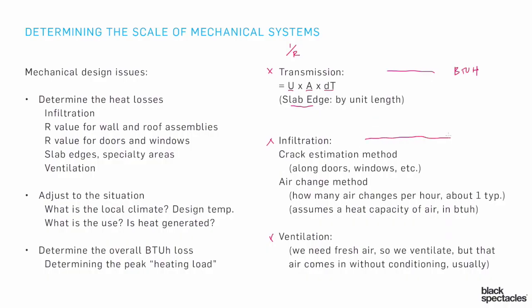The air change method is more of a general approach — certain types of rooms have an approximate air change rate that we know happens by sheer infiltration, so you think of it as air changes per volume of room. Newer buildings tend to be tighter, and some buildings are better built than others. It takes a bit of an art — adjusting based on what you think is likely, knowing the construction, the age of the building, the quality of the contractors, and the level of detailing in the drawings. You adjust to a point where you feel comfortable, do a calculation, and that gives you some BTUH.